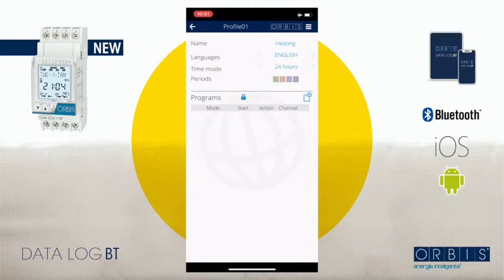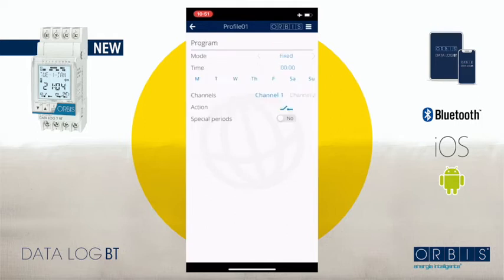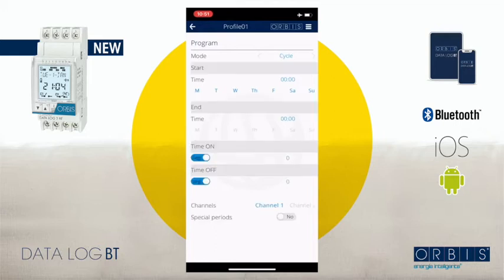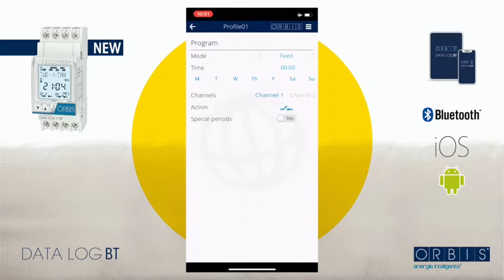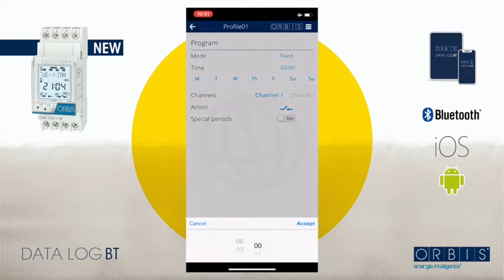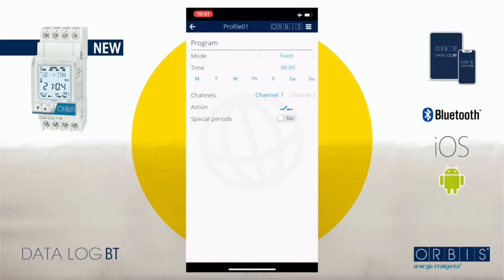We'll talk about periods later, so let's continue with the programs. On the right part we have an icon that is a square with a plus sign, so you click on it and start working. For mode, we have three different modes: fixed, pulse, and cycle, but we are going to start with fixed. For the time, we want the heating to start working at eight o'clock, so you click on zero zero zero zero to define the time and accept.